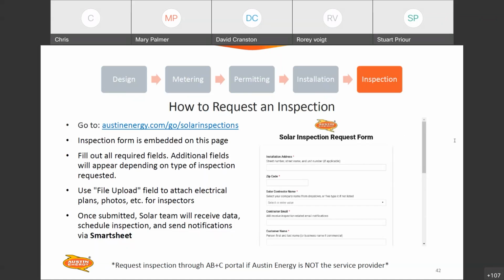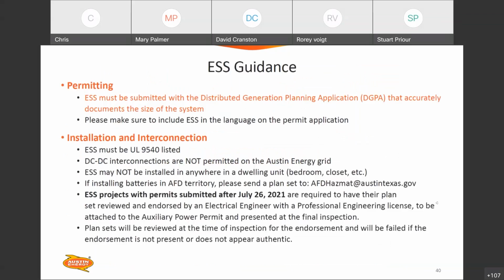Derek is asking: he said the disconnect in the last slide was not feasible - is that still a requirement? You need a fuse disconnect if you're doing a line side tap. Is that what he's talking about? You don't need a fuse disconnect if you're doing a backfeed breaker - you've got to land your solar output in some sort of overcurrent protection, and a breaker suffices.